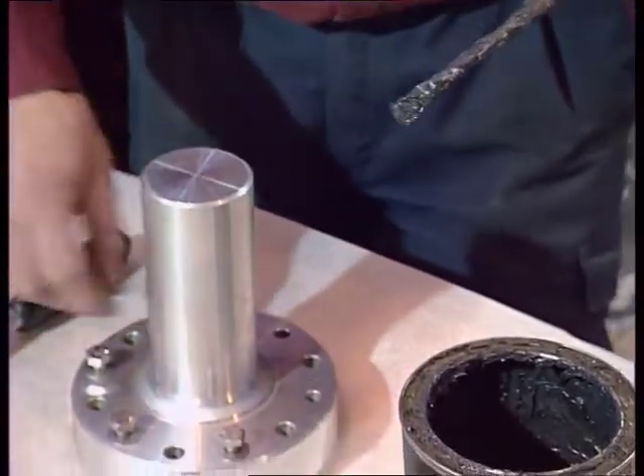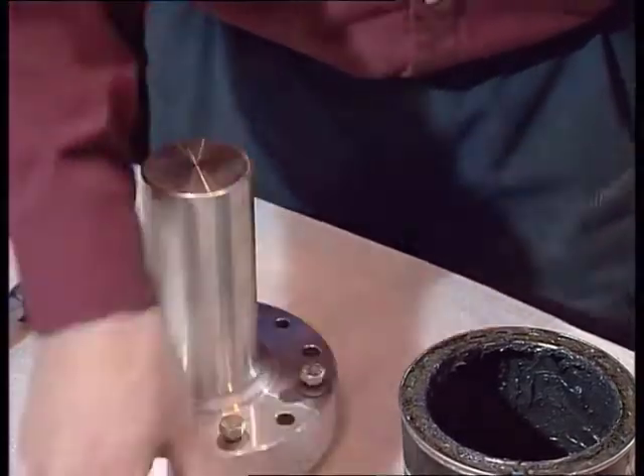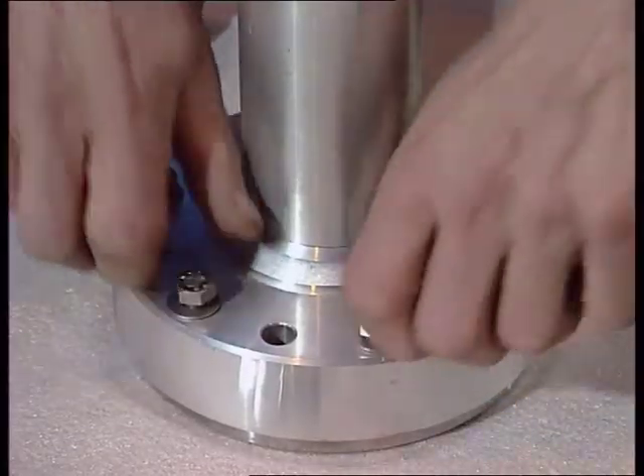Grease all bolt threads and underneath the head with the recommended grease. Insert the M8 screws with the conical spring washers and plain washers which hold the retaining ring. Tighten by hand to press the gasket in place.